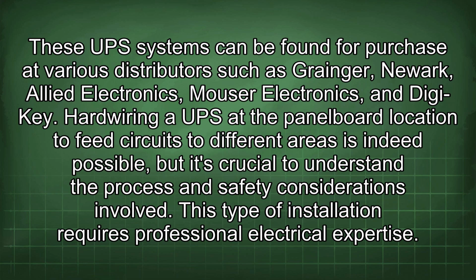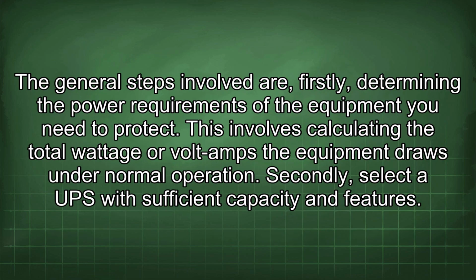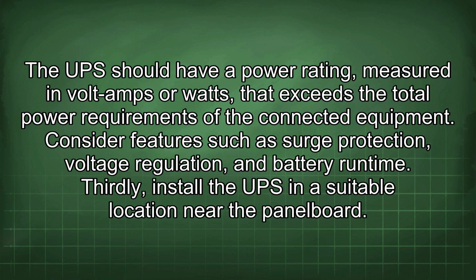but it's crucial to understand the process and safety considerations involved. This type of installation requires professional electrical expertise. The general steps involved are, firstly, determining the power requirements of the equipment you need to protect. This involves calculating the total wattage or volt amps the equipment draws under normal operation. Secondly, select a UPS with sufficient capacity and features. The UPS should have a power rating, measured in volt amps or watts, that exceeds the total power requirements of the connected equipment. Consider features such as surge protection, voltage regulation, and battery runtime.